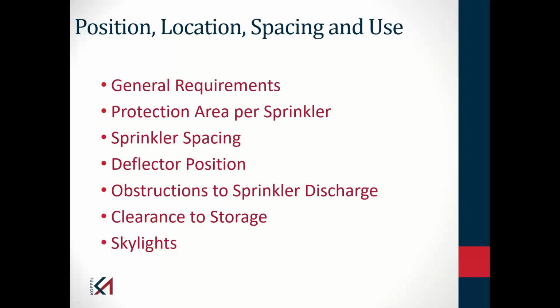Deflector position is how far beneath the ceiling the deflector may be. I won't reveal the educational facility, but in an engineering building at this particular facility, they had removed the lay-in acoustical tile ceiling. They did not reposition the sprinkler. The sprinkler was too far beneath the ceiling. Somebody made the decision to put a square metal pan above the sprinkler, thinking that that would be a heat collector. It doesn't work unless you can tell me the fire is going to be directly underneath that sprinkler.